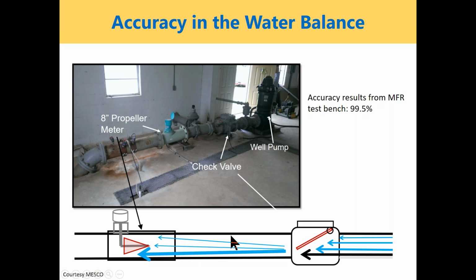The location of that check valve caused some funny things to happen hydraulically, causing the speed of the water at the bottom of the column to be the fastest, where typically it's in the middle of the water column, which is how the meter is designed. It caused the turbine mechanism to overspeed, and the numbers weren't quite looking right, so they had an on-site test done in situ, and that test revealed the meter was actually over-registering by quite a bit.